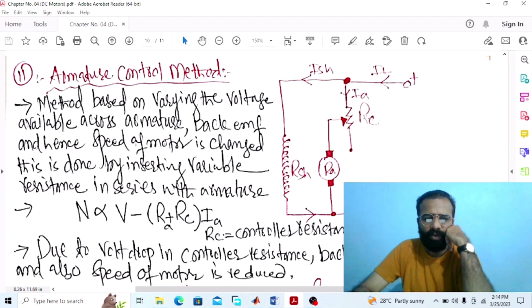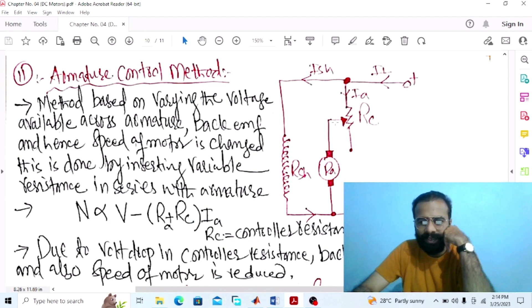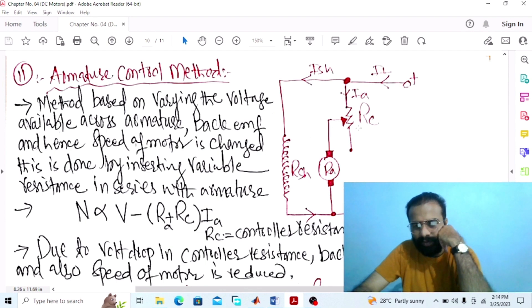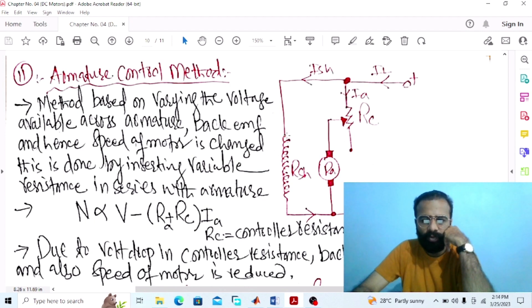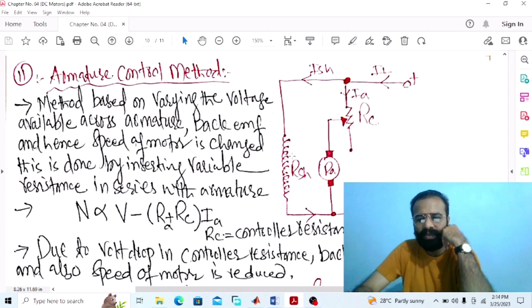This armature control method is based on varying the voltage available across the armature, and hence the back EMF and speed of the motor is changed. This is done by inserting a variable resistance in series with the armature winding. Due to the voltage drop in the controller resistance, the back EMF — which is the voltage available across the armature terminal — is reduced, and so the speed of the motor is also reduced.